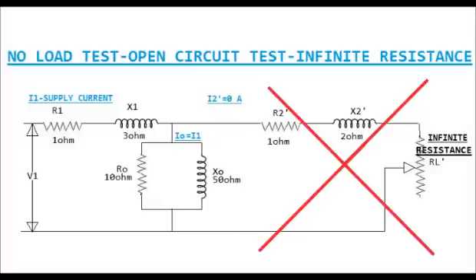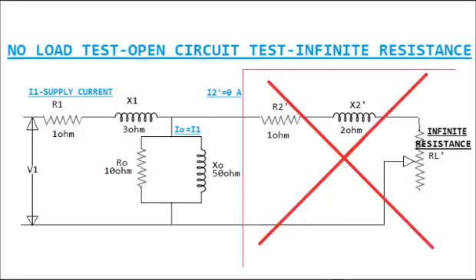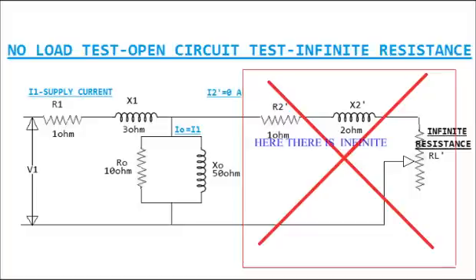In no load test, the resistance of load is made infinite. In induction motor this is made by making slip 0. As there is infinite resistance at rotor side, the current will not flow through R2 dash, X2 dash and RL dash.